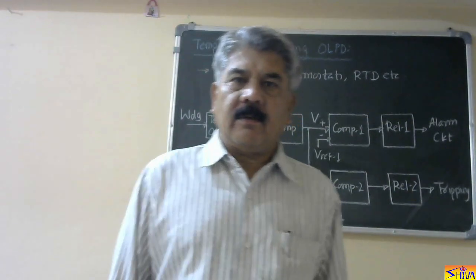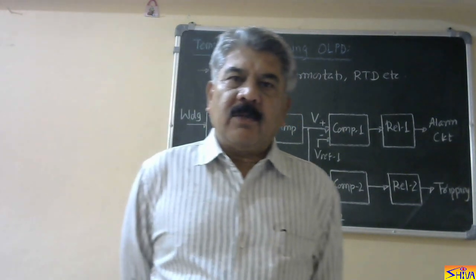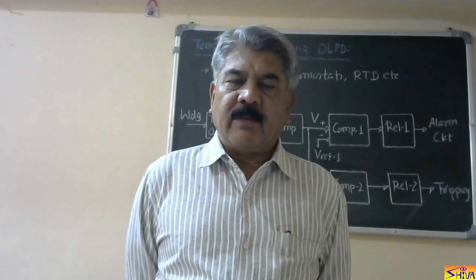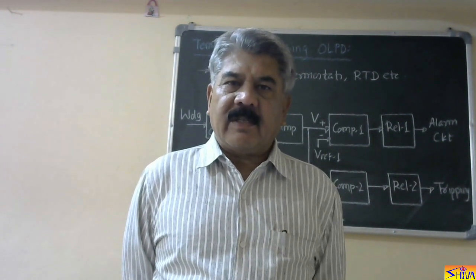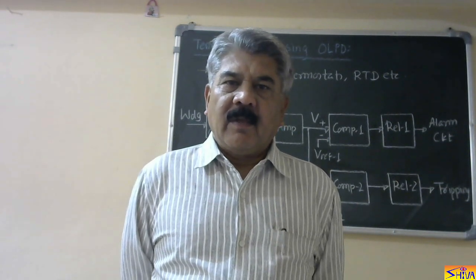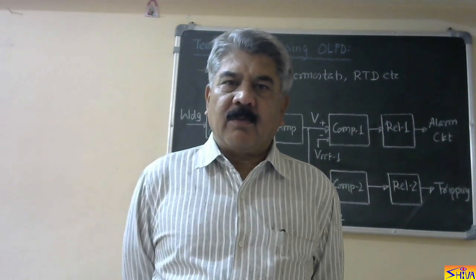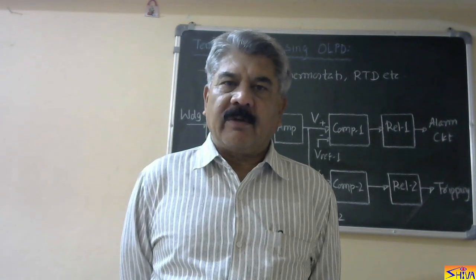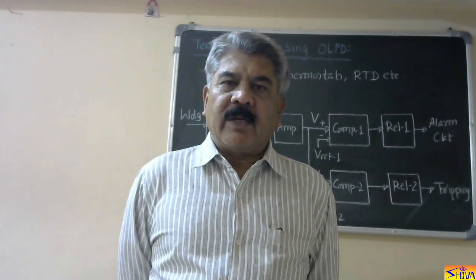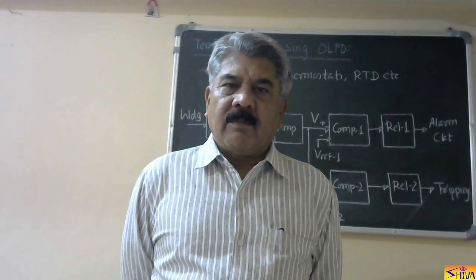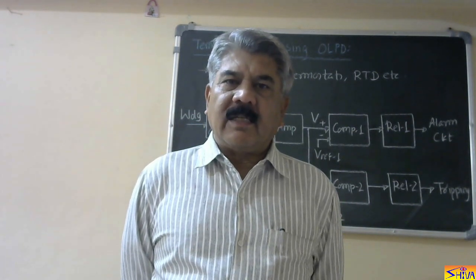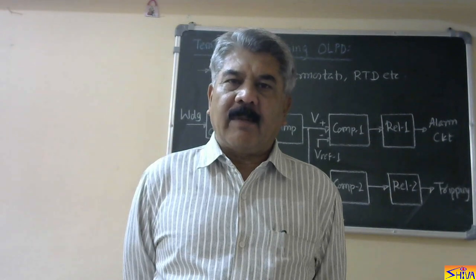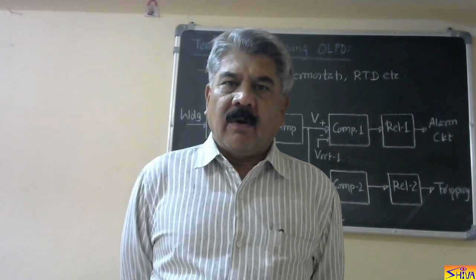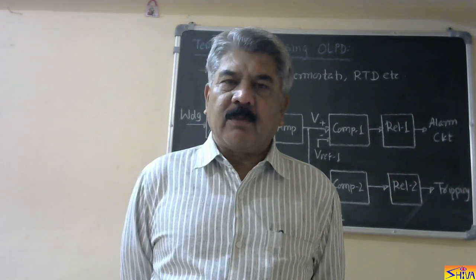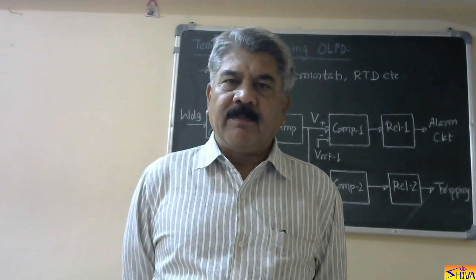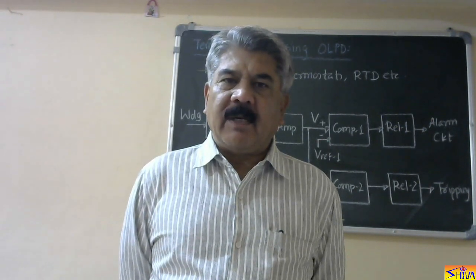Hello friends, good morning. In this unit, that is protection of induction motors, so far I have discussed short circuit protection and overload protection of induction motor by current sensing protective device. For short circuit protection, I had explained protection for very large induction motors, that is provided by percentage differential relay.